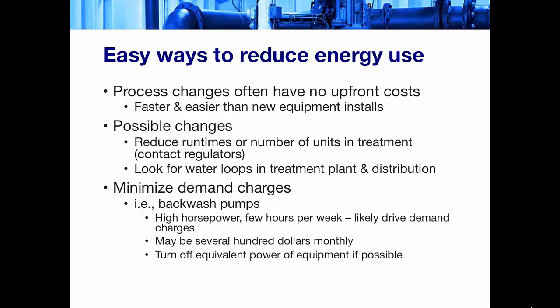Our process changes can eliminate energy use in running something for fewer hours in the day, or looking at when we're being charged the most. So change the way that we operate or the way that we run our system. It doesn't really cost us anything to make those changes, but it can save us money on our energy bills. So looking at ways that we could operate differently is what we want to find here. So we have an example of demand charges being high, and those demand charges are being caused by the high horsepower pumps for backwashing our filters. So when those pumps come on, they have very high demand charges, but the fact of the matter is we only use those backwash pumps occasionally. We don't run them every day. We don't run them every week in some cases. So when those pumps come on, it drives the demand, but we don't need to use them very often.